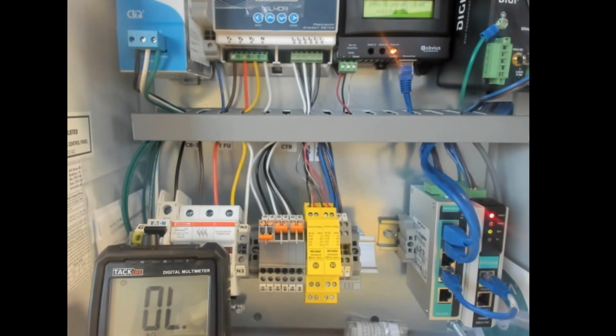Okay. And is there any recommendation for the sales team? Obviously, split cores are easier to work with. Is there any reason that we should sell solid over split on the 5 amp side? So usually you'll only really want to go for 5 amp solid core CTs if you're working in Massachusetts, and that's kind of part of the standard spec for CEC requirements there. So that's an easy way to quote out a project and know you have the basic requirements.